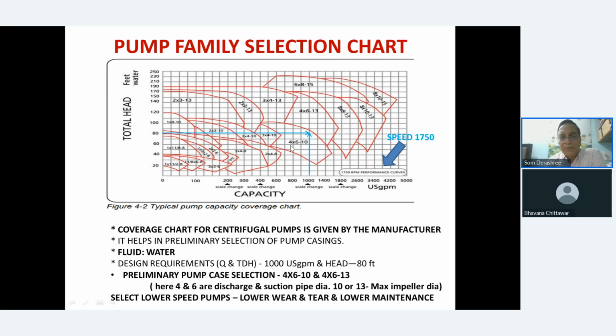Now, what does this 4 and 6 mean? 4 is actually the discharge diameter of the flange of the pump, and 6 is the suction. Suction is always bigger because you need less friction losses. We'll come to it when we talk about the NPSH. Always you will find the suction flange in the pump is larger than the discharge flange. And 13 or this 10 is actually the diameter of the impeller, which is the largest diameter of the impeller in this particular range. So always try to select as low a pump speed as possible so that your maintenance is reduced.